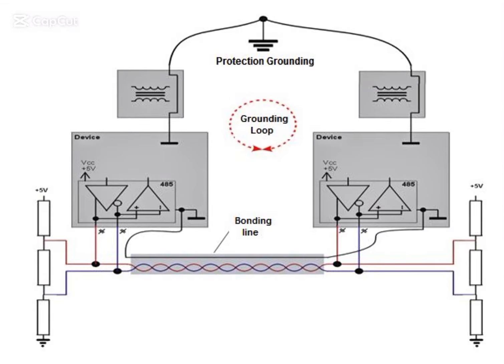In electrical and instrumentation systems, earthing, grounding, and shielding are critical for safety, noise reduction, and proper system functionality. Here's a breakdown of each concept. 1. Earthing. Purpose: provides a safe path for fault currents to dissipate into the ground, protecting personnel and equipment from electric shock. Applications: equipment earthing. Metal enclosures of electrical devices are earthed to prevent hazardous voltages.